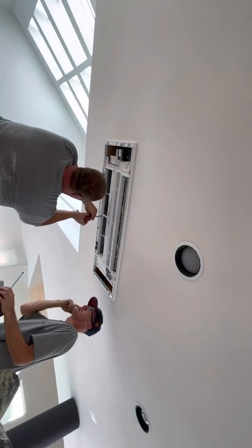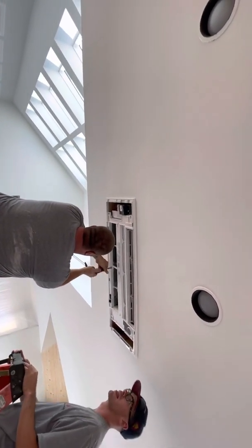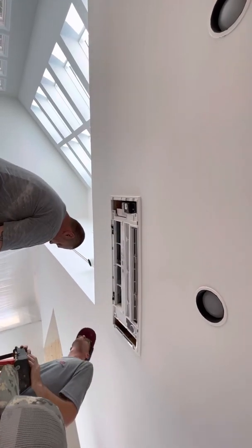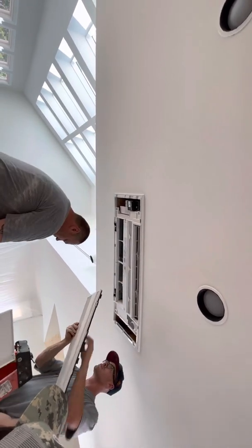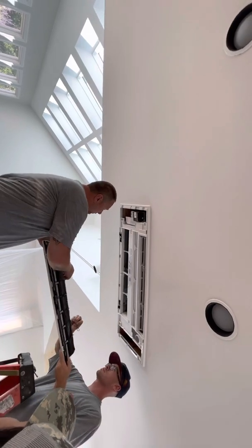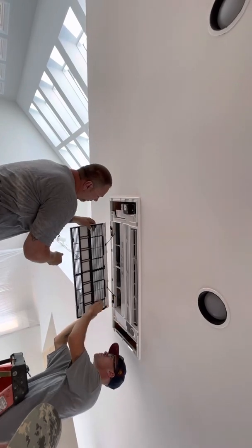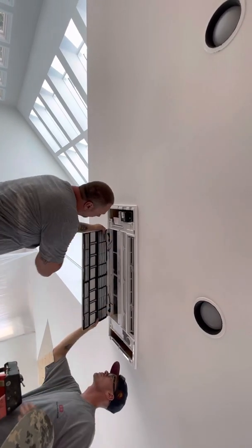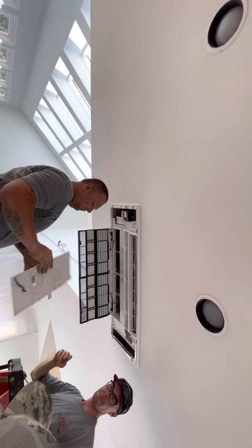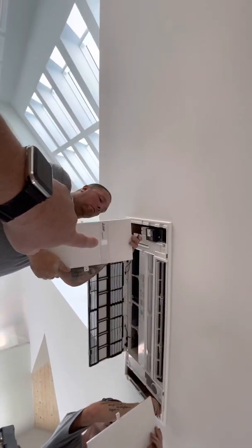That was amazing. Just try not to touch the ceiling too much when you're putting them in. I just want to show you how quick it is to install the cassette — we're right at about five minutes from start to hanging it to it being completed. So they're going to hook the tethers back on. This is the first step into the installation. Then they're going to lock the two locks — they leave it down until you get the outer ones on. These are positional too. If you look at the one Denver has, it has the little window on it.